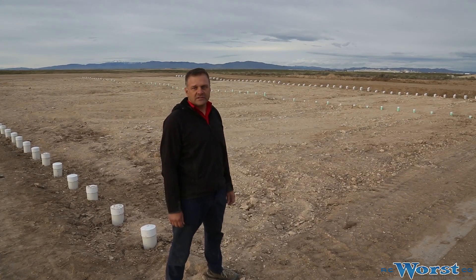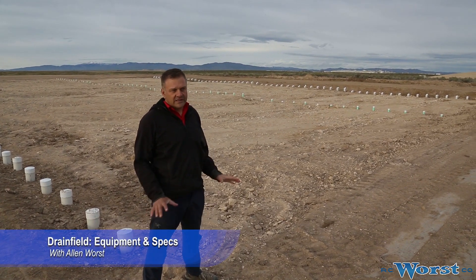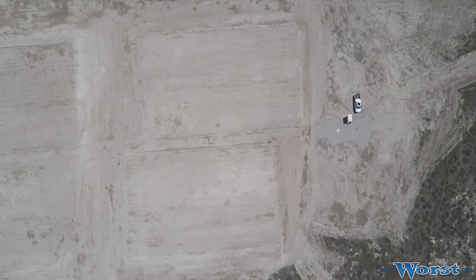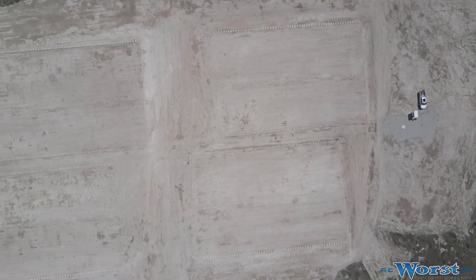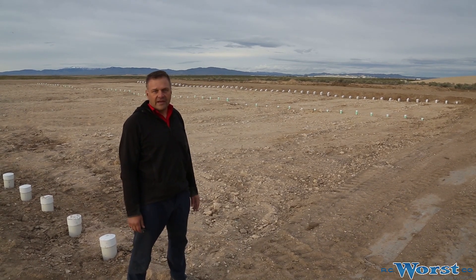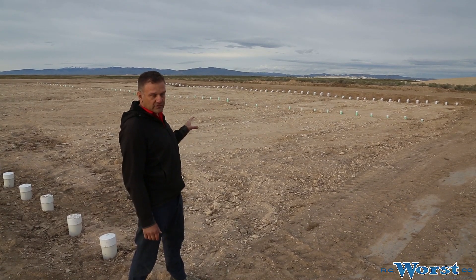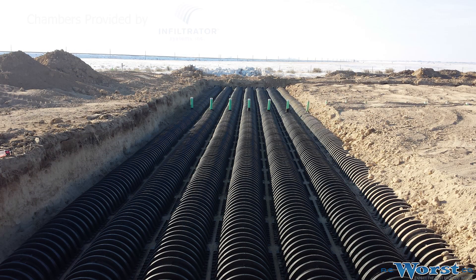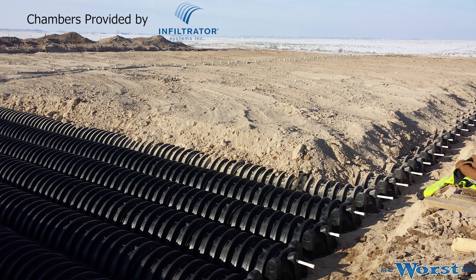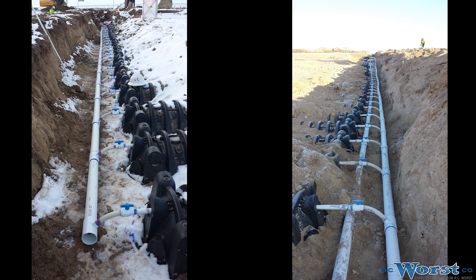We're out here at the CS Beef drain field site. This system was designed and constructed in four modules per the Idaho State IDAPA code for large soil absorption systems. Each individual module is approximately 20,000 square feet, so we've got about 80,000 square feet of actual field. These fields are constructed as beds using Infiltrator drain field product — the Quick4 Standard units — and each lateral is pressurized with a one-inch pipe going down the lateral, using 1/16-inch orifices, so each zone is dosed with one individual pump.